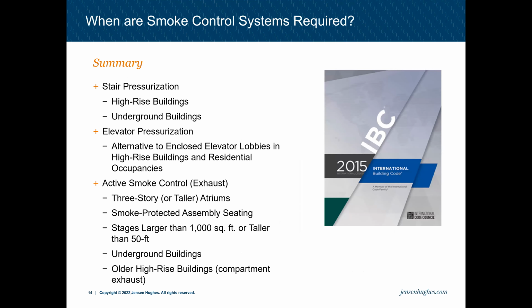So, a quick summary of these systems and requirements. We have stair pressurization required in high-rise buildings and underground buildings. Elevator pressurization, the alternative to enclosed elevator lobbies in high-rise or other residential occupancies. Active smoke control or exhaust systems in atriums three stories or taller. Smoke protected assembly seating, such as your stadiums or convocation centers. Stages larger than 1,000 square feet or taller than 50 feet of roof height. Underground buildings and older high-rise buildings, as compartment exhaust.